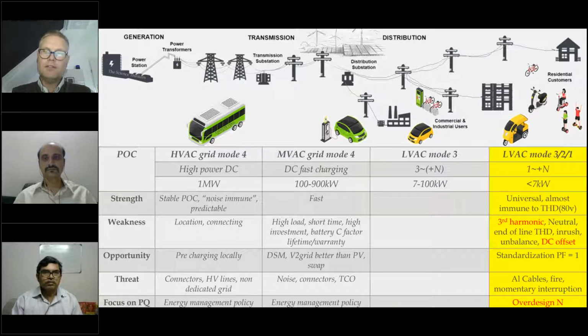And what is very terrible is the DC offset, because when some chargers break down, for instance a diode is damaged, you will get DC offset. In residential homes, you have the earth leakage switch for the protection of our bodies, and those earth leakage switches will saturate when you get a DC current through them, and they will not react anymore. Another opportunity is very easy. I've seen bad chargers, good chargers, and just say in the standardization that the power factor has to be almost 1, and then it will be fine. There's a big threat in cables. When I'm going to accidents, of course we have the 3rd harmonic.